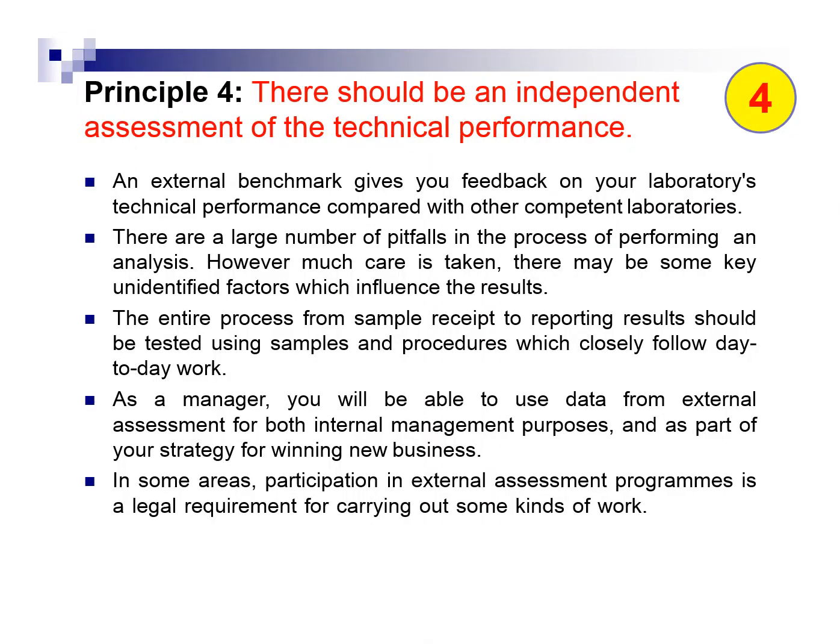Okay, so now move on to principle number 4. So when we talk about principle number 4, basically there should be an independent assessment of technical performance. So class, independent assessment of technical performance is something like an external benchmark, which gives you feedback on your laboratory's technical performance compared to other competent laboratories.